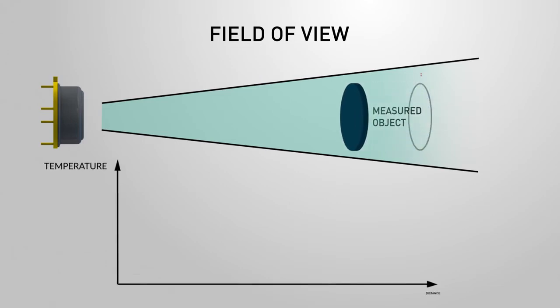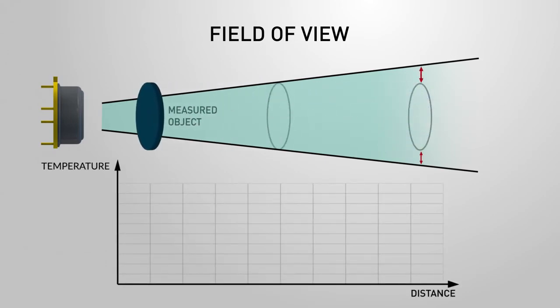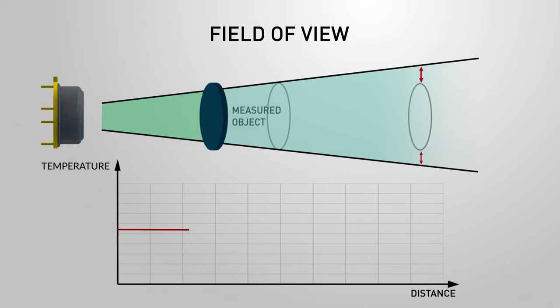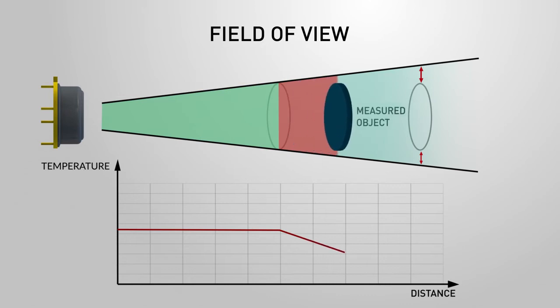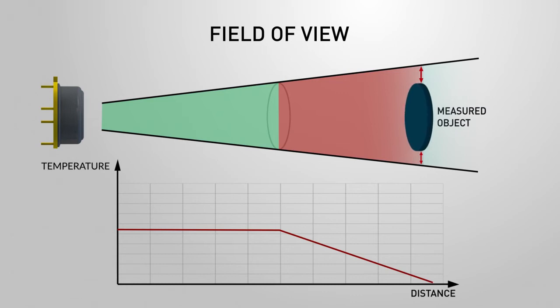It's important that the measured object completely fills the field of view. If this is not the case, the sensor can detect objects that are not supposed to be measured, resulting in an incorrect measurement. Good understanding of the field of view is advised when designing an application with far infrared sensors.